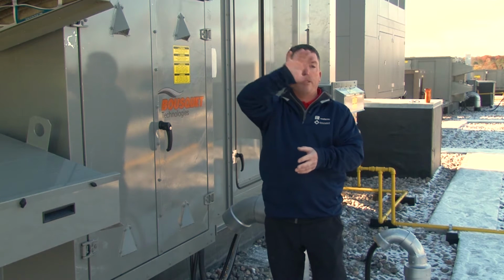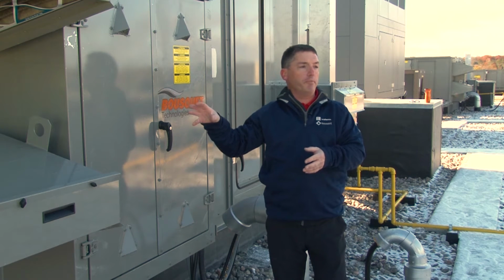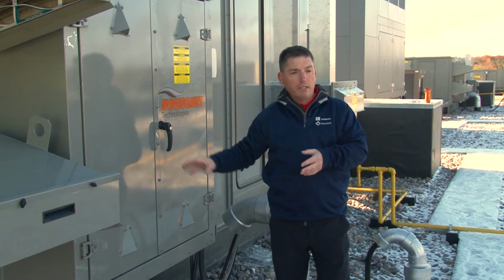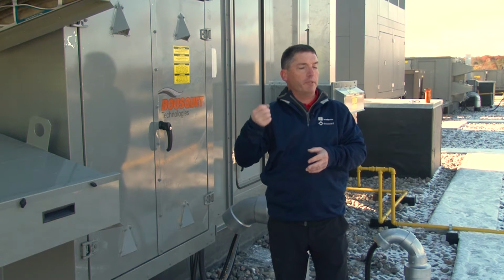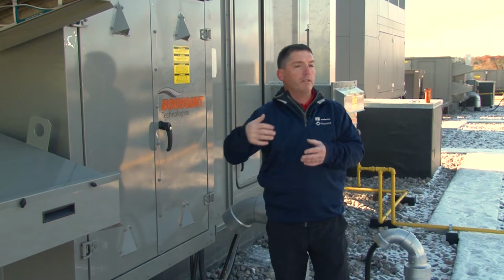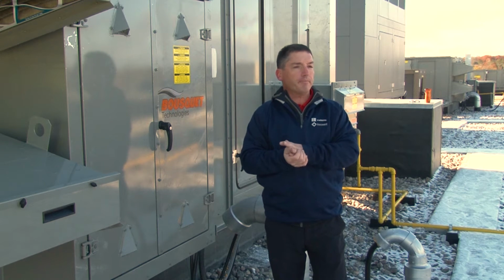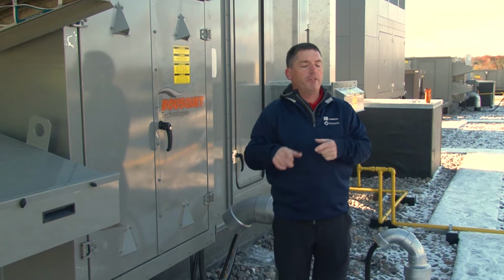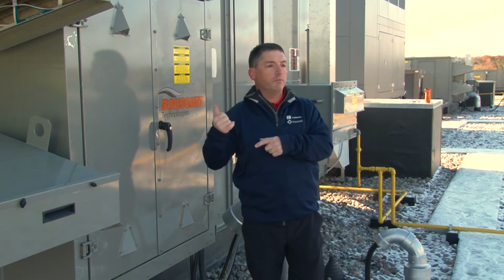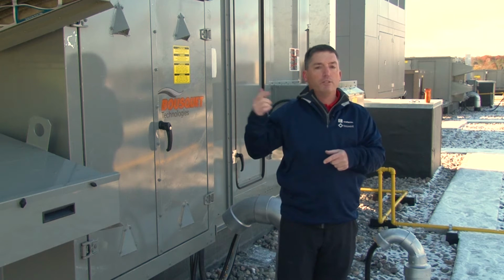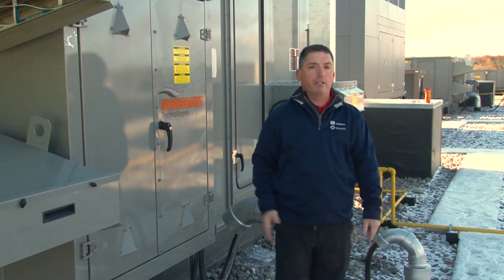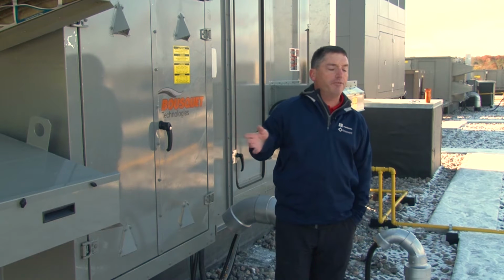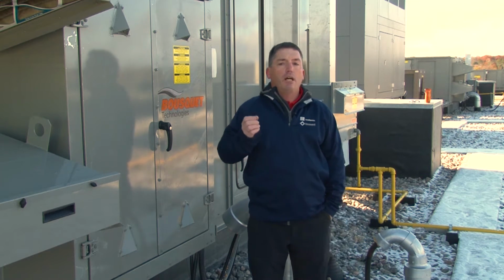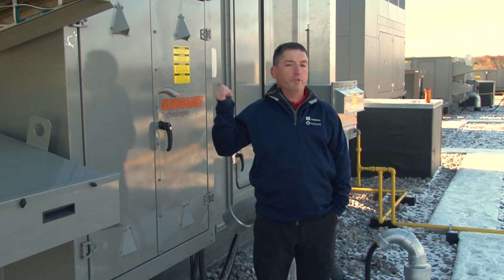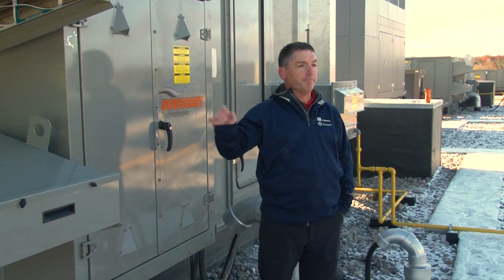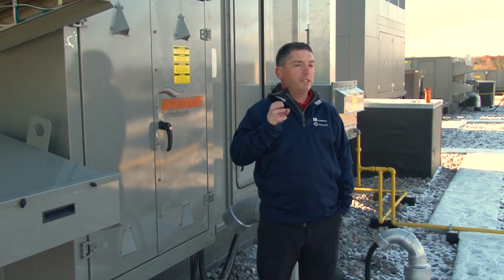So the way it works is, as that wheel rotates, it absorbs heat from the warm exhaust. Then as it rotates around into the incoming airstream, it transfers that heat into the cold air, preheating it, which reduces the overall heating load. Same functionality in the summertime. We're exhausting cooler air than what we're bringing in, so we get a little bit of recovery on the air conditioning side. That wheel itself is virtually maintenance free as long as you maintain the return air filters and the outside air filters. That wheel will stay clean.